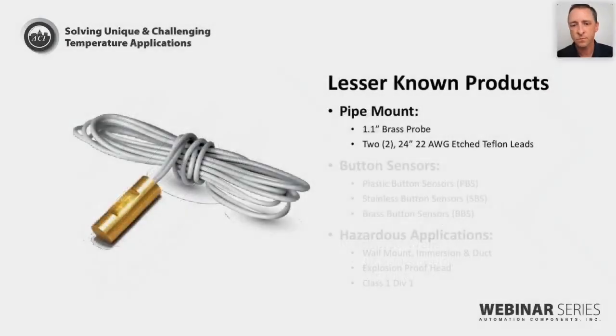One of our newer configurations is what we call the pipe mount, and it's shown here on the left side of the screen. It's a short 1.1-inch brass probe, and it's a bit hard to see from this photo, but right there where the cursor is, it's a crescent-shaped probe. So for small pipes, say less than 3 inches in diameter, that crescent shape provides a great contact between the sensor and the pipe to very accurately measure the temperature from within that pipe.